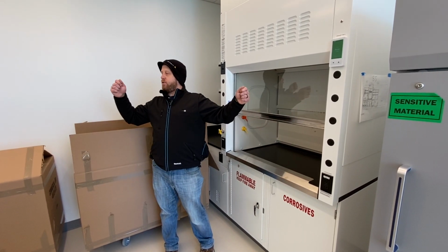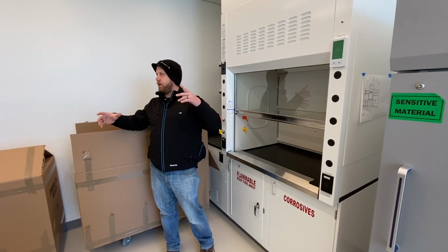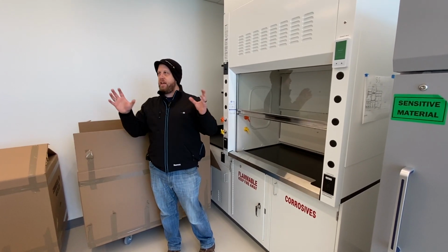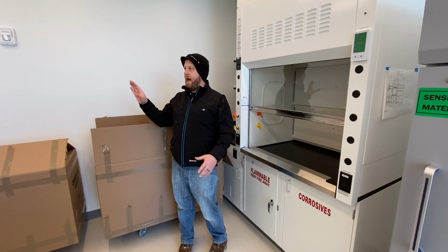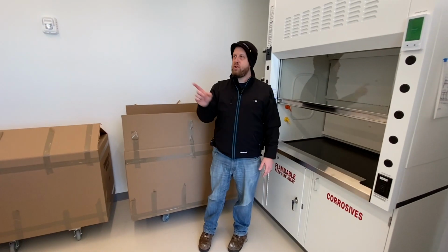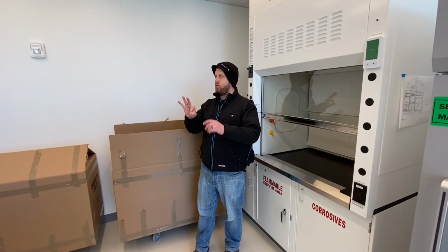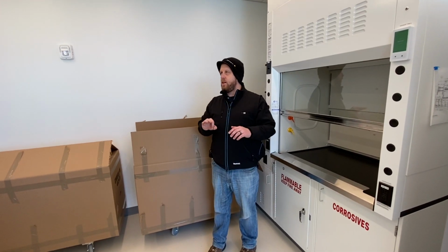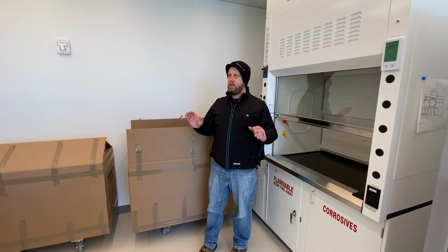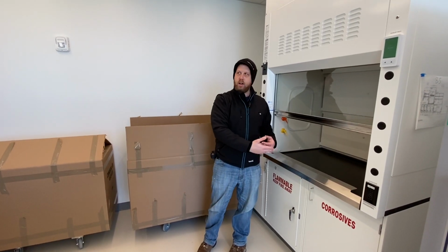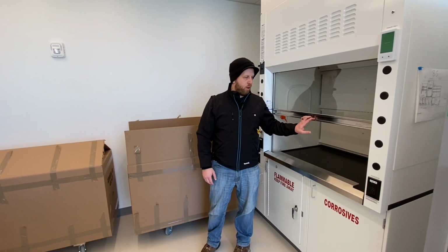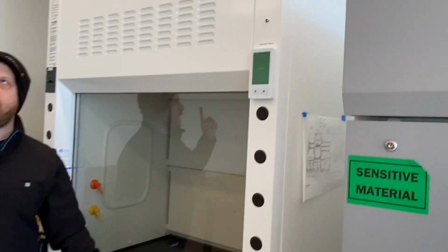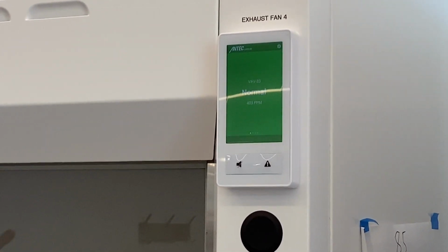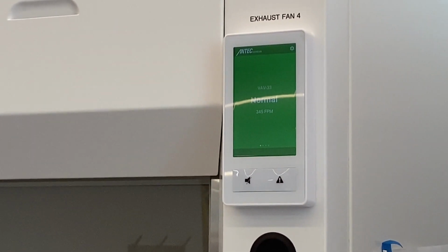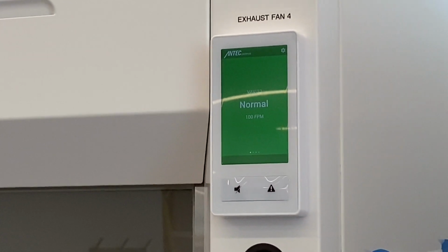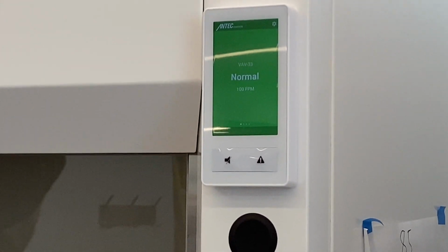Now, what happens is they need to keep this room at a slight negative, as we were mentioning earlier. So as more of these increase and more of the fume hood exhaust air valves open up, what's going to happen is that we need all the air coming in this way, so we're going to restrict the general exhaust, because you've got to remember there are three types of air valves: supply, general exhaust, and fume hood exhaust. Because these are all opening now, the general closes, so now we force more air through the fume hood. And as these all close, the fume hood exhaust air valve above the ceiling will then also close, and the general exhaust air valve can open up more. So that's how the lab air system works, and it's all based on pretty much reacting to these, to make sure that the air goes through the fume hoods.